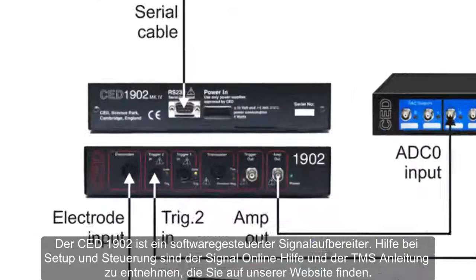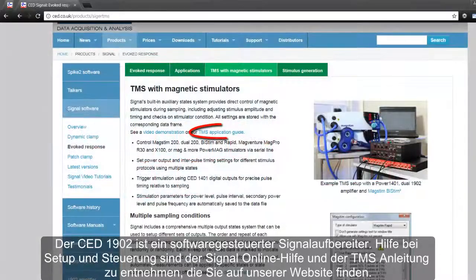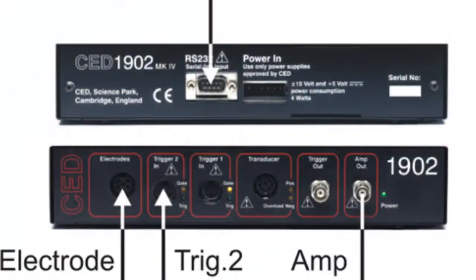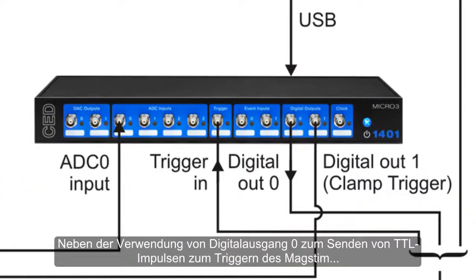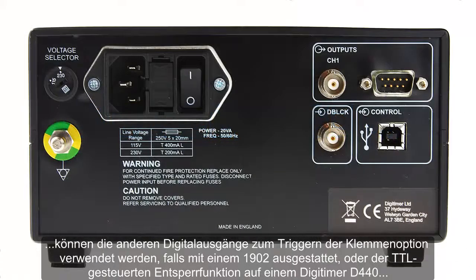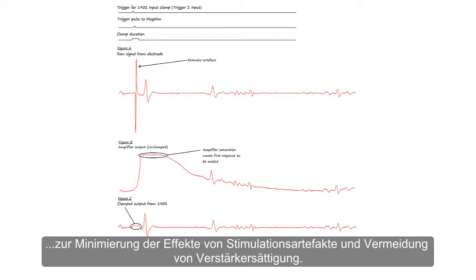The CED1902 is a software-controlled signal conditioner; help with setup and control can be found in the Signal online help and in the TMS application guide downloadable from our website. Signal also has software support for Digitimer D440 and D360 amplifiers. In addition to using digital output 0 to send TTL pulses to trigger the MagStim, the other digital outputs can be used for triggering the clamp option if fitted to a 1902, or the TTL gated deblock function on a Digitimer D440 for minimising the effects of stimulation artifacts and preventing amplifier saturation.